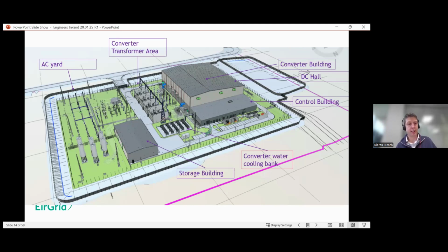This is done through IGBTs, a lot of electronic switching, with a very sophisticated control system. The output is AC electricity, which comes into the middle of the site where we have our transformers - 3 single phase operational transformers and 1 single phase spare, should there ever be a faulted phase unit in the future.